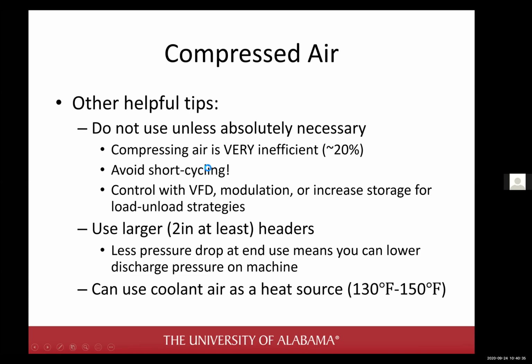This says avoid short cycling. If you have a load and unload compressor and it's kicking on and off a lot, there could be something wrong. You might need more storage in your receiver tank. Short cycling can actually cause damage to your compressor over a long period of time, and it's also inefficient, because you have to blow out your sump every time you do that. Avoid short cycling if you can. If you can use VFDs, please do.